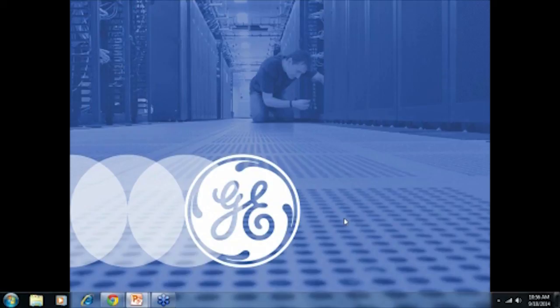Some people are using flywheels, and the flywheel will last the life of the module, so that can have an impact. Typically, you have to have a very long life cycle to make the economics of a flywheel work, but there are some customers that are looking at using flywheels just because you don't have the recycling of batteries, and they're doing it for environmental purposes, not necessarily economic purposes. But those are the major things that would impact the overall cost and the TCO based on the UPS module. Great. Here's another. Why do UPS systems use so much energy during their lifetime? Aren't they mostly backup power that is rarely used? Is the energy for trickle charging?